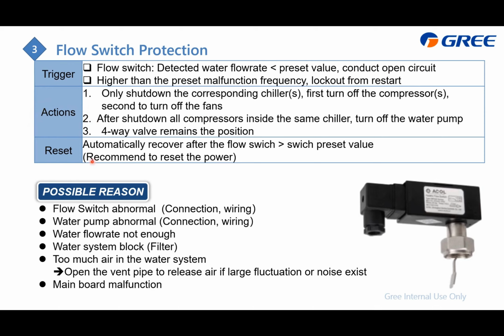And it is the same. So here are the possible reasons. First, maybe the flow switch is abnormal, so just check the connection and the wiring. Maybe the water pump has something wrong, or the water flow rate is not enough. This time, just check the inside water pressure.